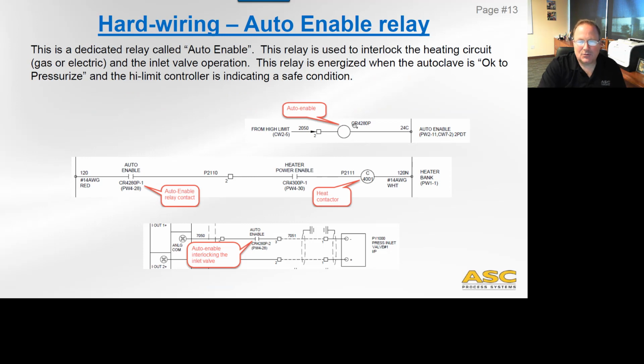Okay, and so that relay is then tied to all your heating contactors to keep heating from occurring, and it is there as a permissive for the pressure inlet signal coming from the 4 to 20 milliamp from the PLC. And so the auto enable relay is basically the thing which is going to stop addition of pressure and addition of heat. Okay.